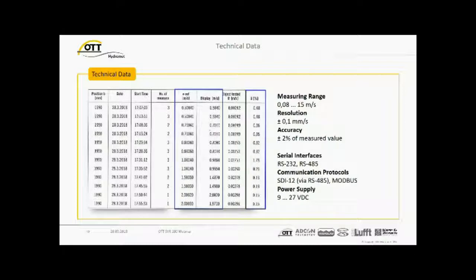So they took the instrument to the carriage and the rating tank, the tow tank, and they did several tests with different velocities, starting with 0.08 up to 2 meters per second. And for each carriage run, the accuracy was confirmed to be less than 2% of the measured value. This was a very great result. We are very proud of it and can provide you a certificate if you want.